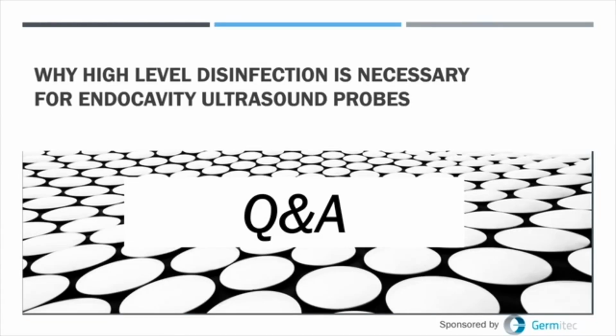The first question: if the probe cover does not tear, do I still need to disinfect the probe before the next patient? The answer to that question, which is an excellent question, is yes, for several reasons. One, multiple studies have shown that probe covers may fail, have inapparent, and I want to say that again, inapparent holes or leaks you're not aware of.